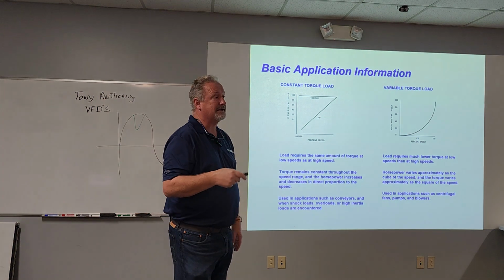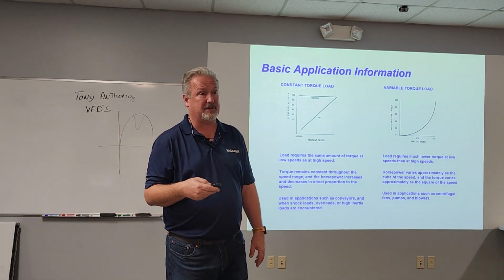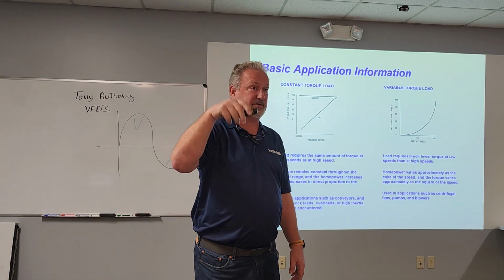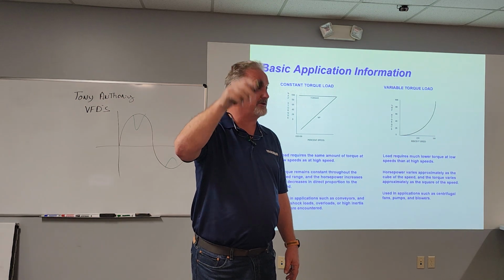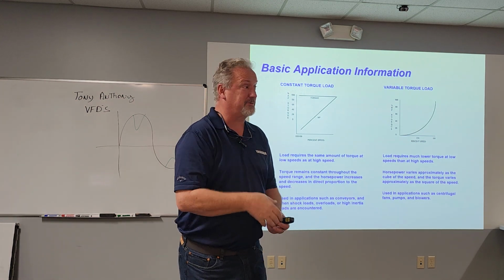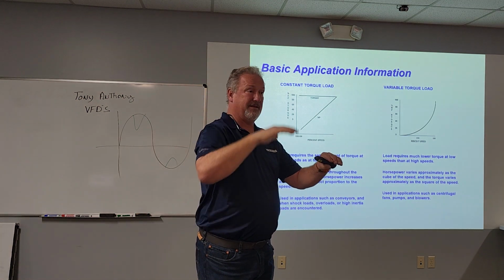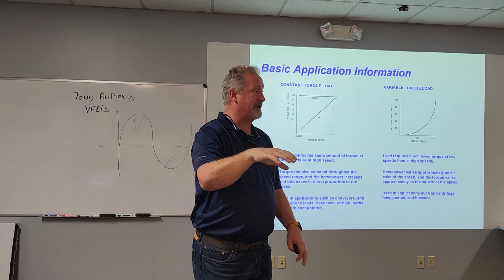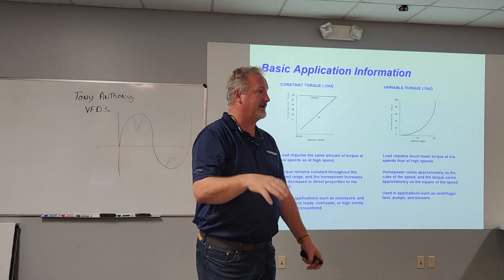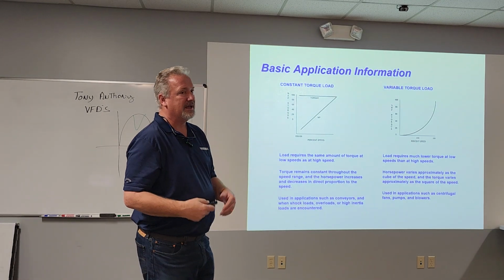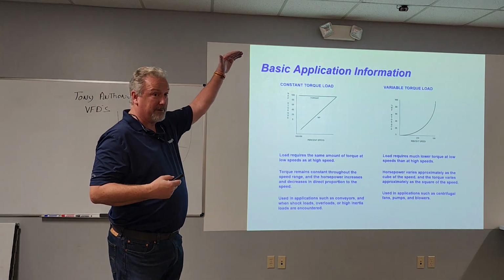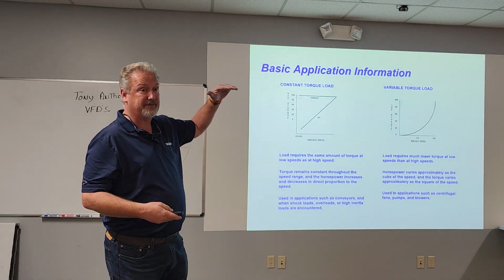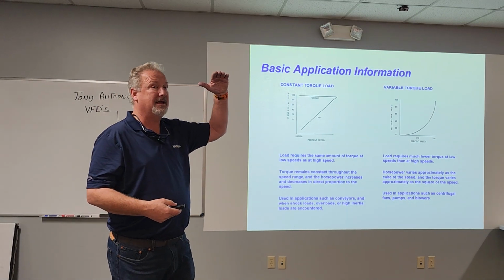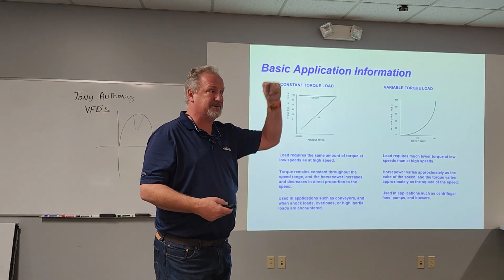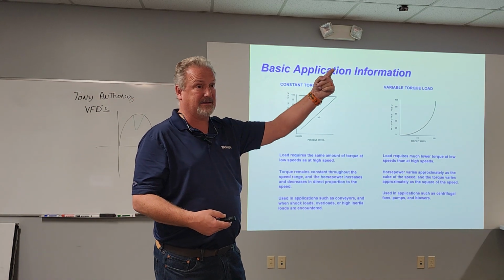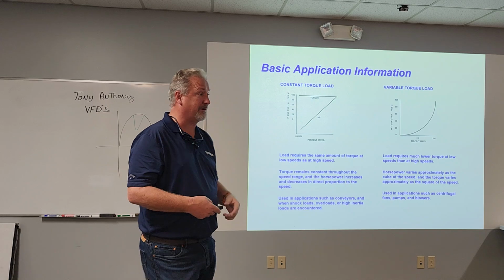But power is the cube of it. So if you drop it 20%, that's 0.8 times 0.8 times 0.8. That's why 20% gets us 50. At 30 hertz, you're like 20%. And that works the other way too, as he was saying, the affinity laws go the other way. If you go above, every hertz you go up is the cube of that in power and torque required.